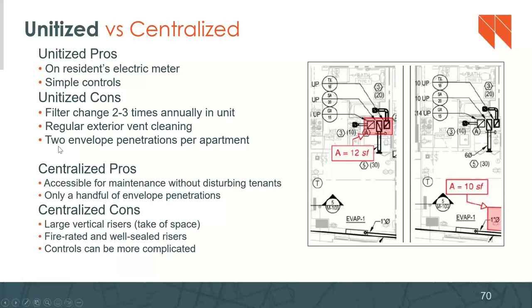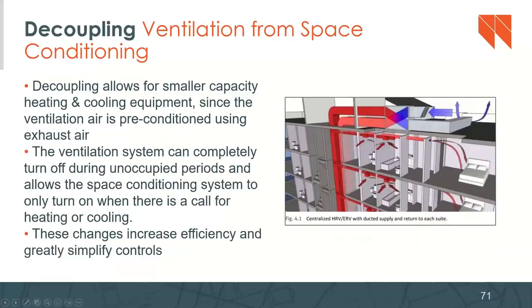And then the centralized, so the big fan on the roof, the big HRV or ERV on the roof, it's very accessible for maintenance. You don't have to get into anybody's apartment, and it's only got a couple of envelope penetrations. And then of course, the centralized cons: it takes up space for all of these large vertical risers. The risers and all the ductwork have to be fire rated and very well sealed. And then the controls can be quite a bit more complicated as well.